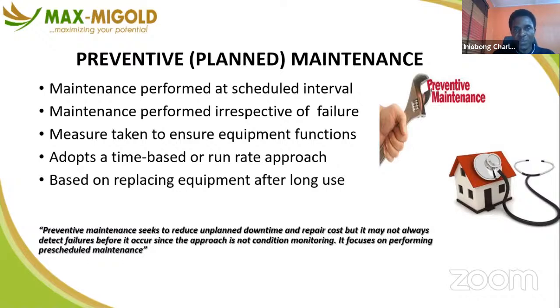It adopts a time-based or a run-based approach. This kind of maintenance strategy can be time-based, like every 2 months, or run-based. For example, a good benchmark for maintaining a generator can be every 250 hours of run time, so after every 250 hours you carry out servicing on that generator.